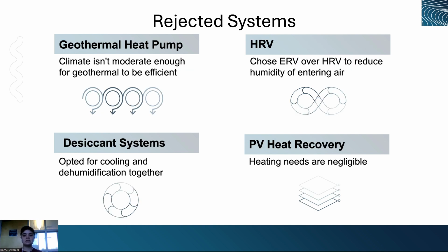As for systems that we didn't use, we looked into geothermal heat pumps. But we ultimately decided that the climate isn't moderate enough for heat pumps of that scale to be efficient. We also considered an HRV, but chose an ERV over the HRV to reduce the humidity of the entering air. We also looked at desiccant cooling systems, but we opted for both cooling and dehumidification together. And then since we are using solar panels on the roof, we did look at PV heat recovery. But we ultimately decided that since our heating load is negligible and we basically just need hot water for showers and personal use like that, we decided not to go with that system.